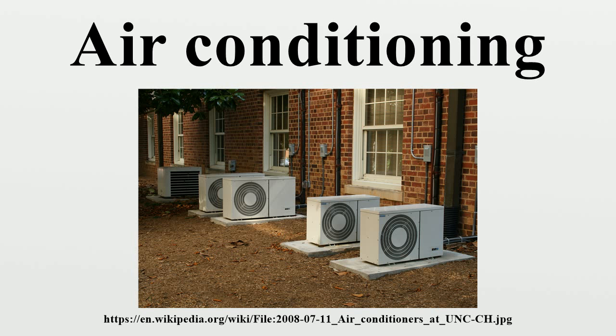This is because ice forms on the outdoor unit's heat exchanger coil, which blocks airflow over the coil. To compensate for this, the heat pump system must temporarily switch back into the regular air conditioning mode to switch the outdoor evaporator coil back to being the condenser coil, so that it can heat up and defrost. A heat pump system will therefore have a form of electric resistance heating in the indoor air path that is activated only in this mode in order to compensate for the temporary indoor air cooling, which would otherwise be uncomfortable in the winter. The icing problem becomes much more severe with lower outdoor temperatures.